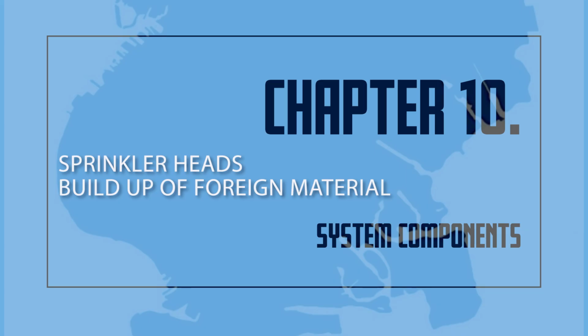Scouring or acidic liquids are likely to damage the sprinkler heads and should not be used for cleaning. Hot solutions of any kind should never be used to clean the sprinkler heads. Removal of protective caps and straps on glass bulb sprinklers shall be performed at the time of installation.